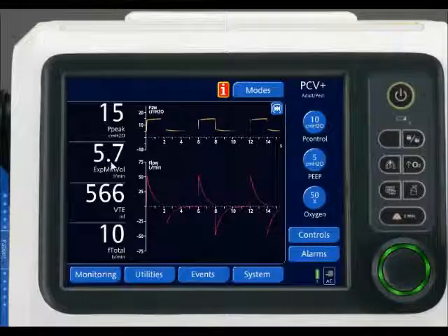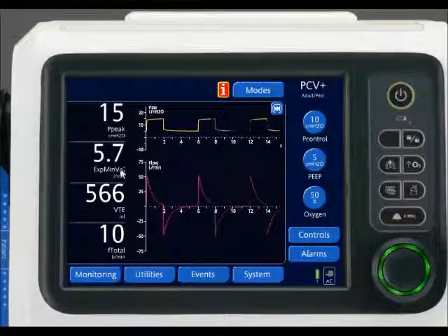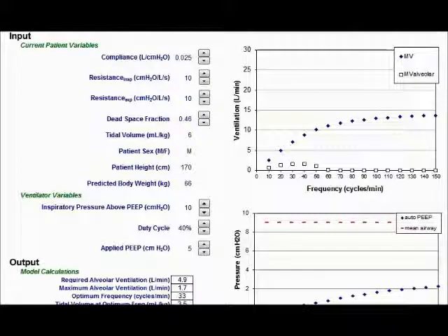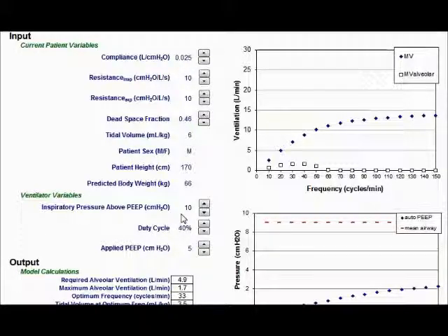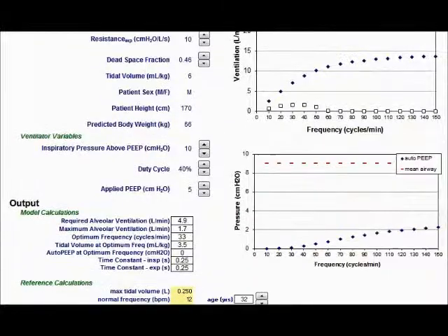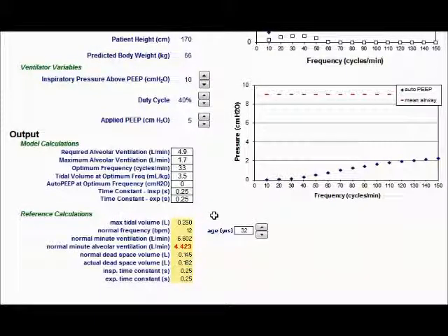So this is the first scenario — a normal patient with pretty average compliance giving about 600 cc. Now we're going to go into a different scenario. I changed the compliance of the patient to reflect a patient with ARDS. I decreased the compliance from 60 to 25, which is a common compliance for an ARDS patient. We kept the same inspiratory pressure of 10 centimeters of water, and now my max tidal volume obtainable is only 250 cc.